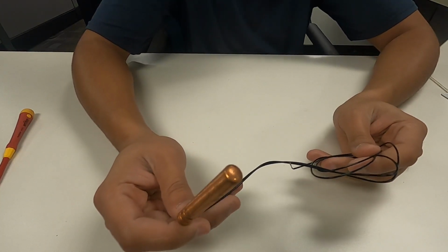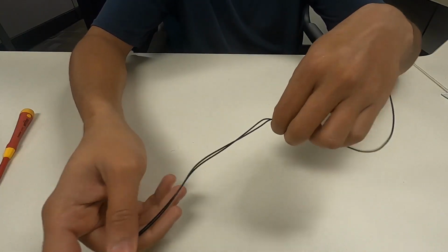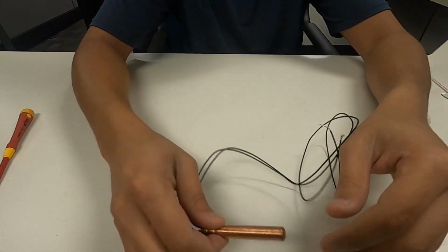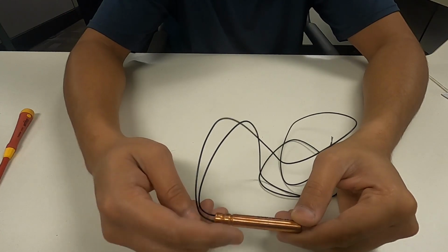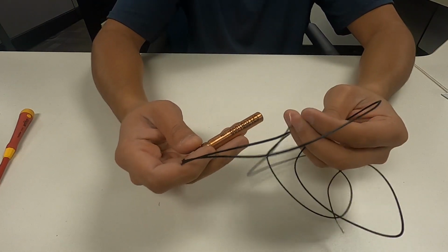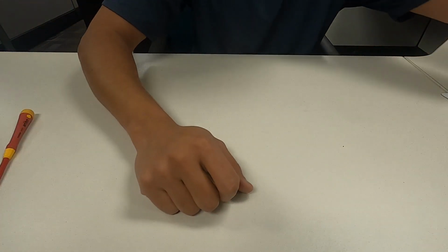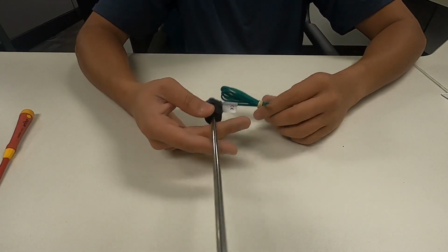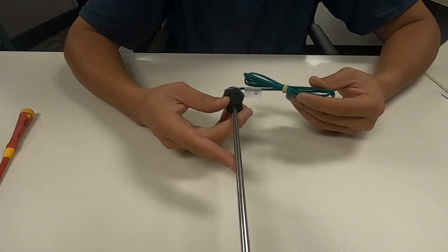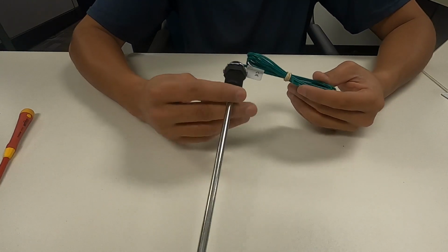Coming to humidity. Let's go to humidity. Now, the humidity sensor, the same as before, can be duct mounted or wall mounted. And the signal type for the humidity sensors will be either 0 to 10 volts, a voltage signal, 2 to 10 volts, a voltage signal, or 4 to 20 milliamps, which is a current signal.